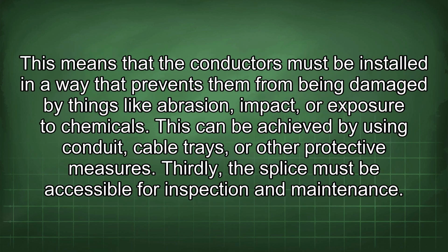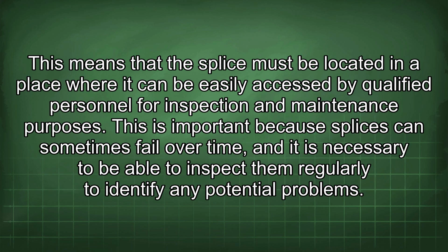This means that the conductors must be installed in a way that prevents them from being damaged by things like abrasion, impact, or exposure to chemicals. This can be achieved by using conduit, cable trays, or other protective measures. Thirdly, the splice must be accessible for inspection and maintenance. This means that the splice must be located in a place where it can be easily accessed by qualified personnel for inspection and maintenance purposes.